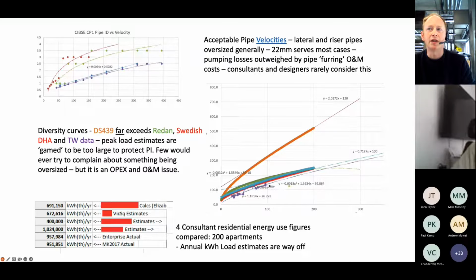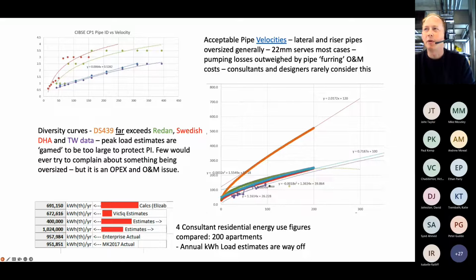You get fan coil units that are undersized for the appropriate delta, really, because that's the cost thing, but they're generally oversized for their duty. And the net result is that you can actually, with fan coil units, reduce their flow temperature without adversely affecting the response time. But truthfully, it would be better to get them sized correctly to begin with. And a lot of it stems from load estimates right at the outset, which are incorrect based on real world data, because a lot of consultants don't tend to feed that back.